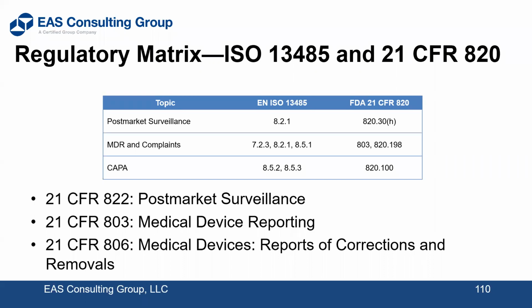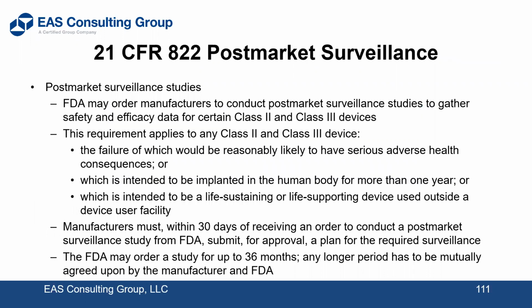Then comes Part 822. That's the post-market surveillance that I mentioned about. That's where FDA tells specific firms, those usually high-level class 3 medical device companies, to go ahead and submit these data to them. So that's one that you have to do only if FDA tells you to do that. Again, these are high-level products done by risk. That's because FDA sees, or with these data, that there could be a problem with these products. Again, the life-saving, life-supporting implanted products, very high class 2 and 3 medical device products.